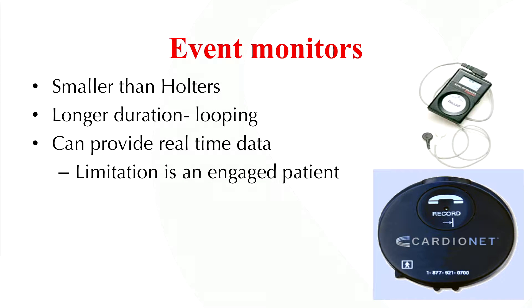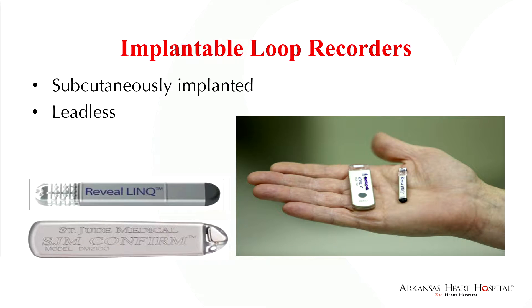Event monitors, or looping event recorders, are smaller than Holter monitors. They continuously record information, and when a patient experiences a symptom or an arrhythmia meets pre-specified criteria, the device will record anywhere from 60 to 90 seconds worth of data. This can provide almost real-time data, transmitted either through a trans-telephonic mechanism or now more commonly through a cellular mechanism.